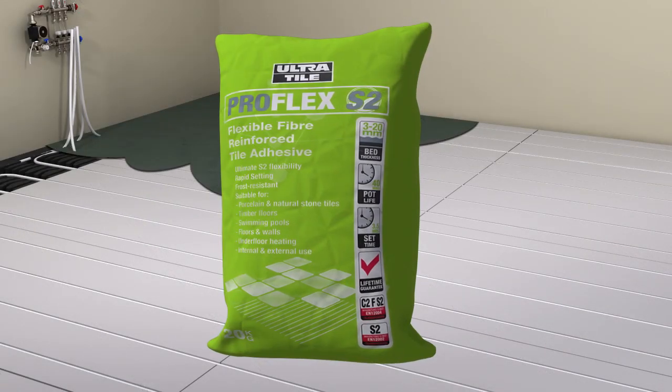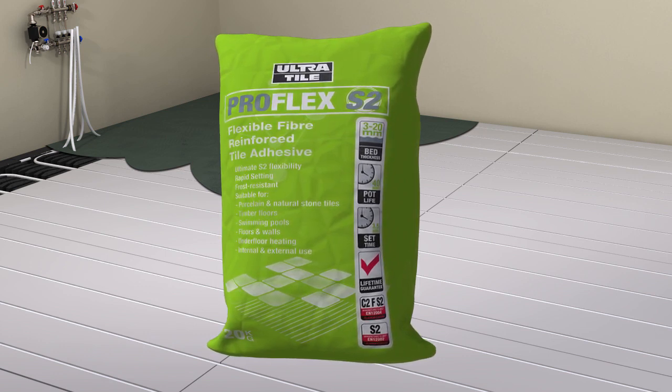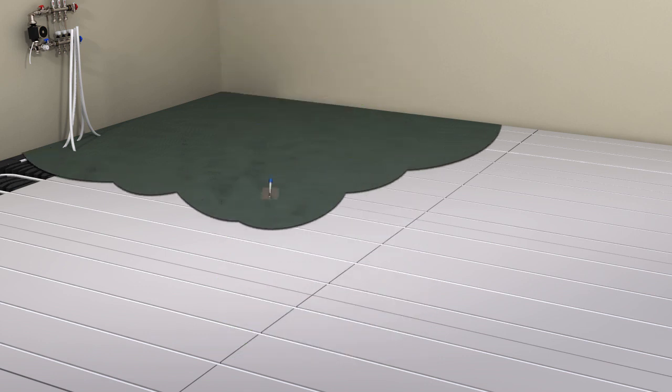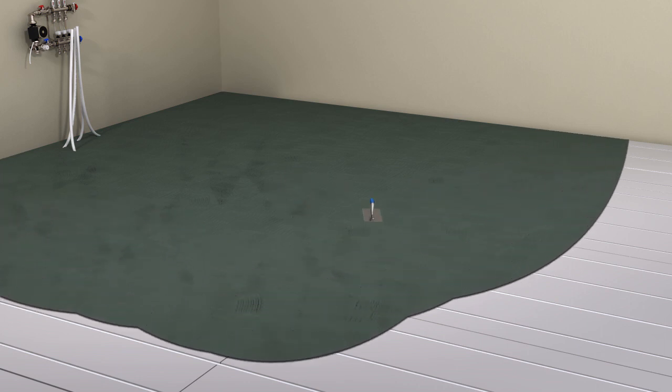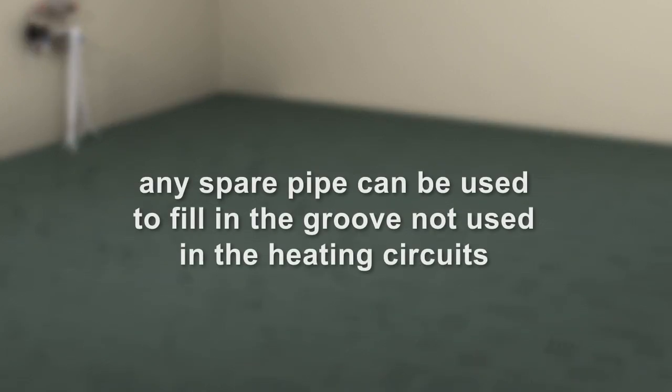Fix the tiles with a 3-5mm coat of Ultra Pro Flex reinforced S2 adhesive using a notched trowel. This must cover all of the board, inclusive of the grooved area where the pipe has not been installed. Any spare pipe can be used to fill in the groove not used in the heating circuits.